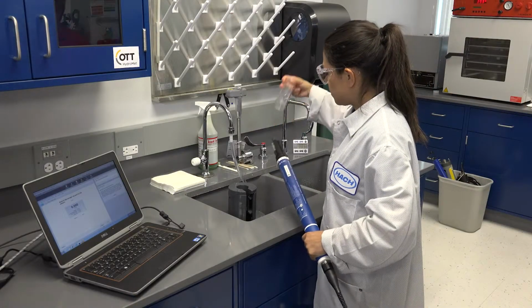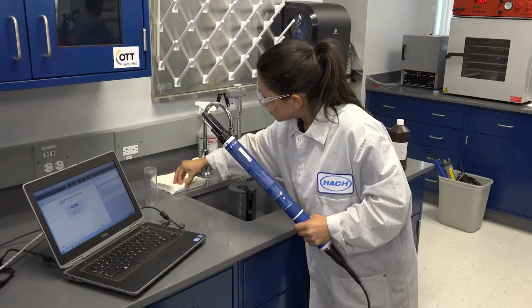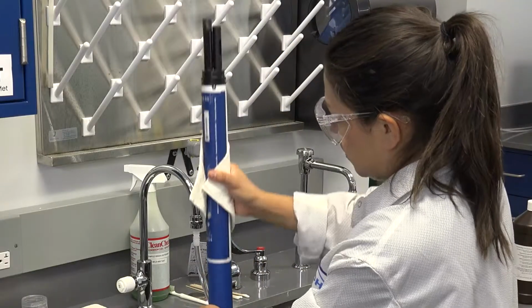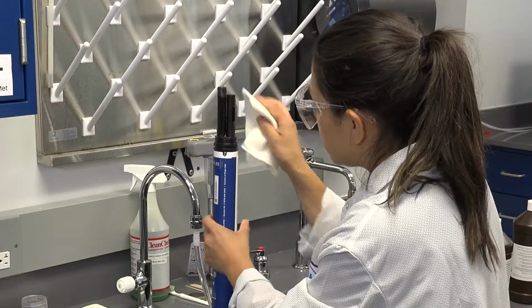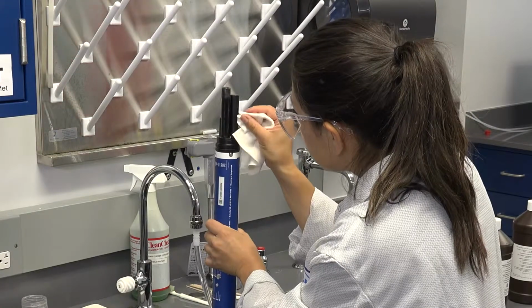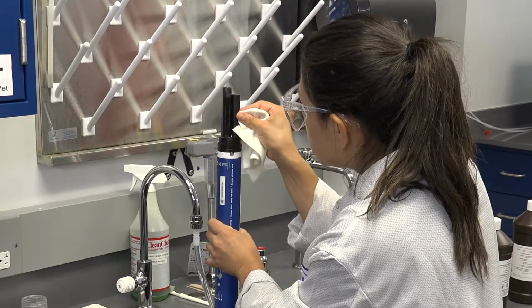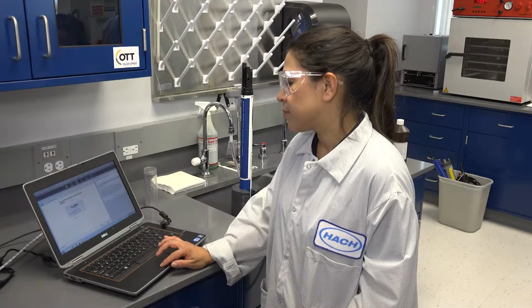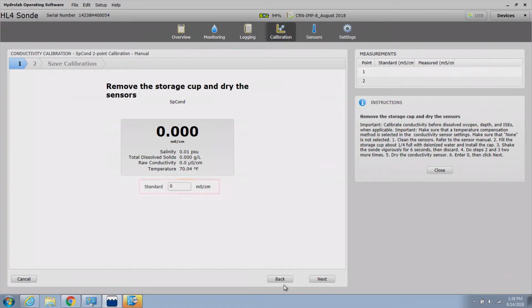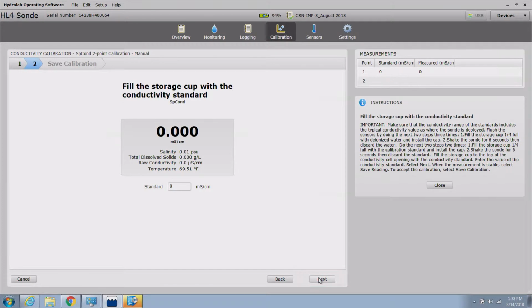Ensure all sensor maintenance has been performed prior to calibrations. For the first conductivity calibration point, the sensor must be completely dry to achieve the 0 reading. Enter the number 0 into the standard text box. Click Next to proceed. The stabilization process will begin and must complete successfully before proceeding to the second calibration point. To achieve the best results, the second calibration point should be higher than your expected conductivity value during the deployment.